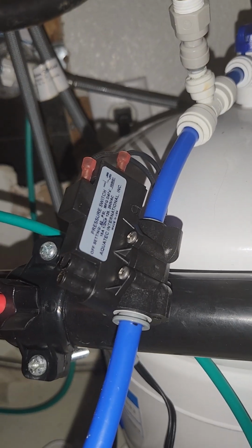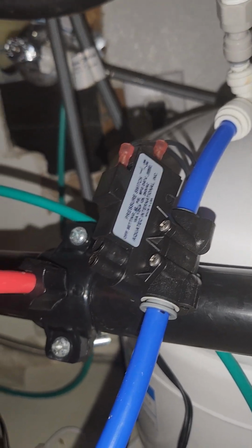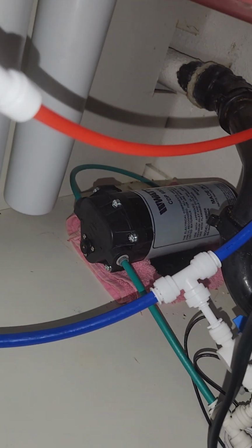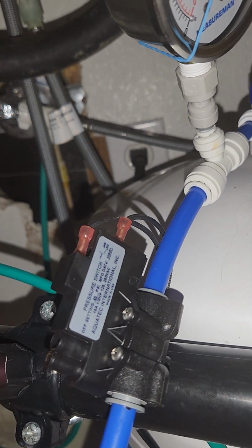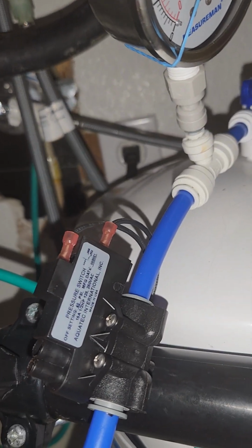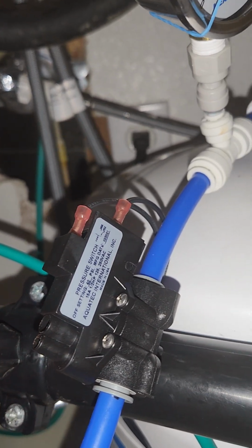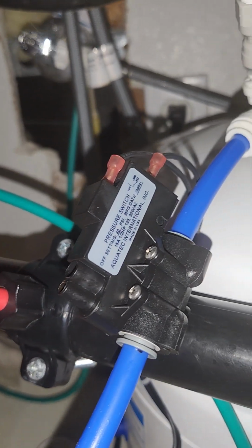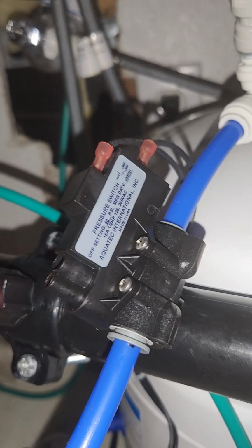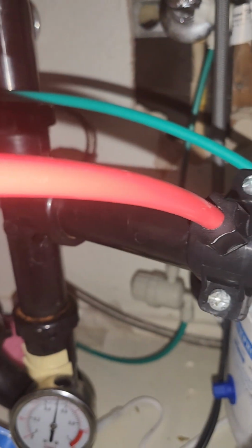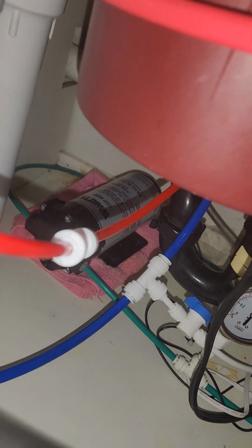And there's a pressure switch that is a combo with this booster pump. Once the pressure reaches some set point, which is set here and controlled using a hex wrench, it sends a signal, and then the pump stops. So there's a pressure range in which it operates. The RO system is not operating all the time, and that's how it works.